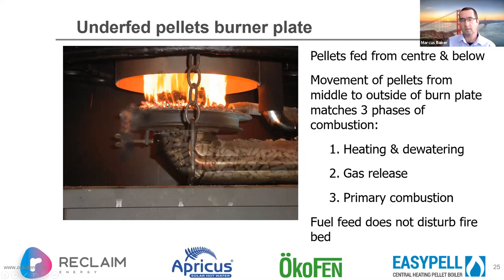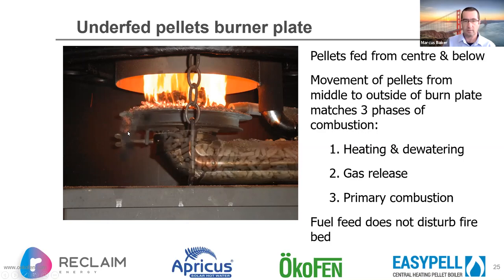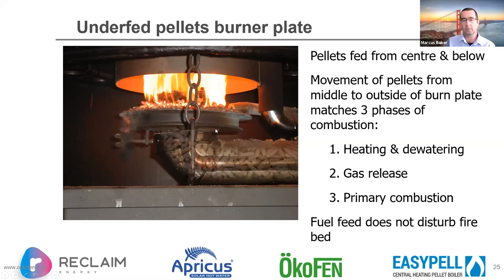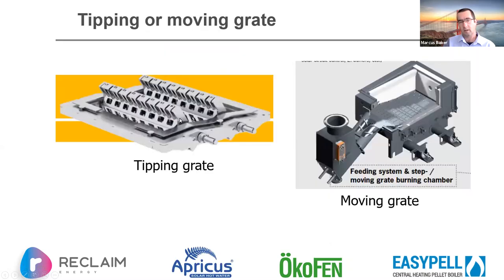There's a marked color difference in the pellets as they move out into the gas release and carbonization phase, then combustion occurs and ash falls off the side. In the Ökofen context the grate itself doesn't move — pellets move off the grate. The round grate gets a shimmy, pushed backwards and forwards, to ensure ash works off. Other approaches include a tipping grate where everything slides off, or a moving step grate as seen in the KWB boiler.